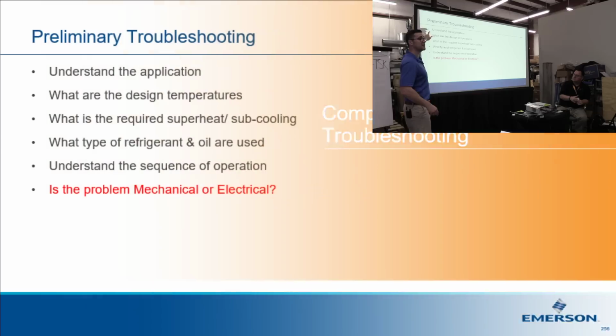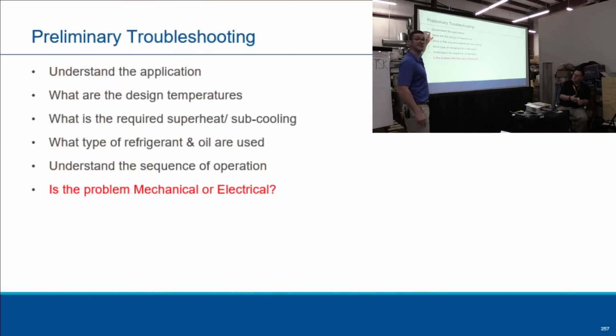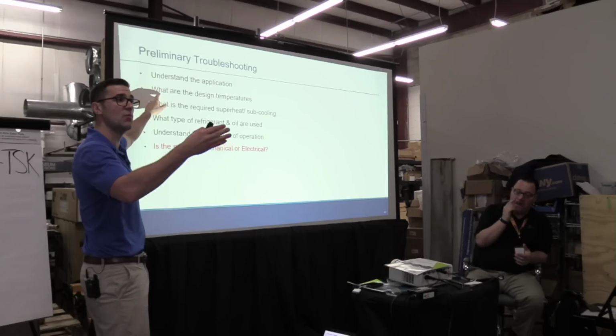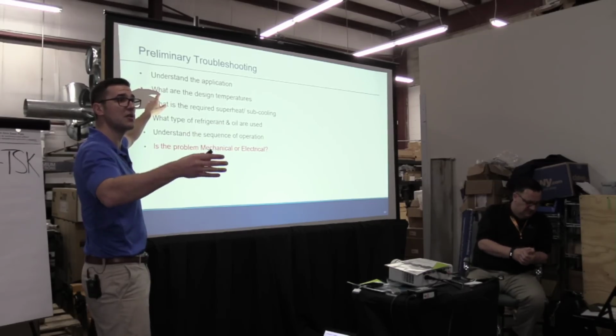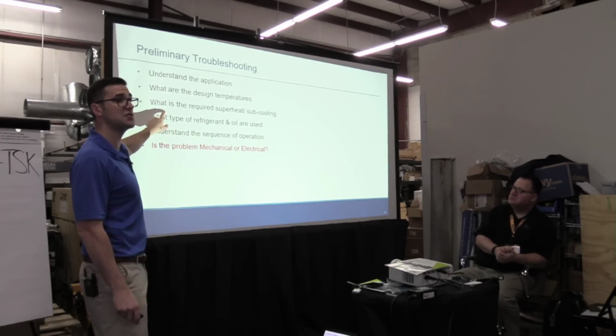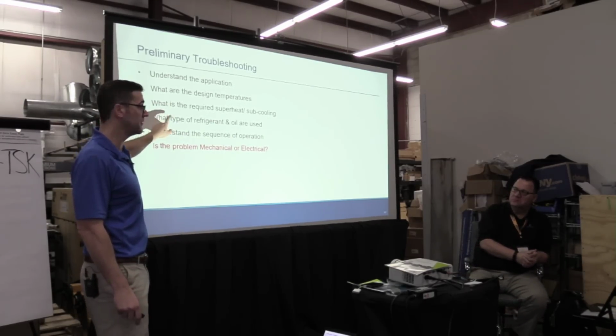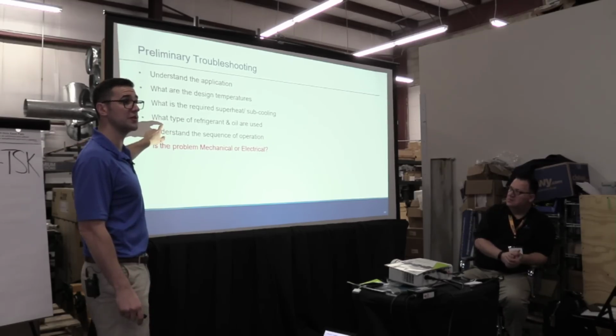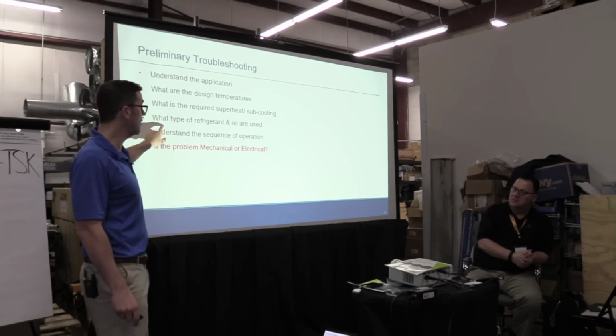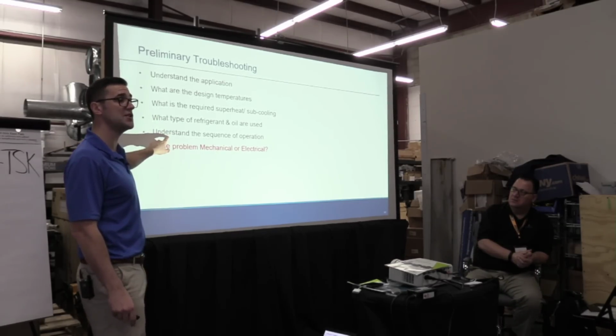Compressor system troubleshooting. I'm going to go through a few of these. You really need to understand the application. Okay? What are the design temperatures? We talked about it. Is it supposed to be 20 and 120 or 45 and 130, whatever? What is the required superheat and subcooling? You need to know this stuff. What type of refrigerant oil is used? It's very important.